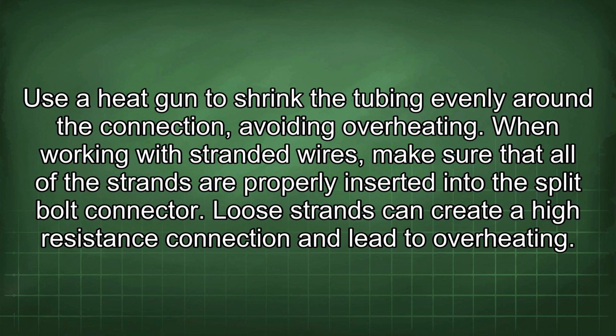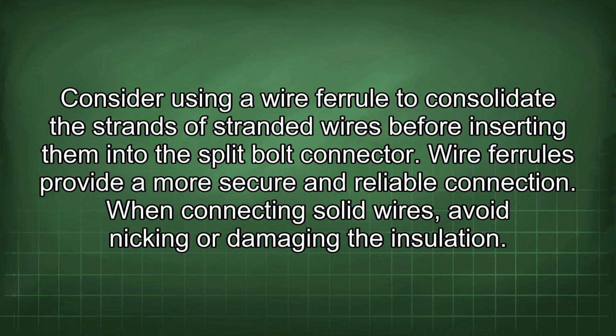When working with stranded wires, make sure that all of the strands are properly inserted into the split bolt connector. Loose strands can create a high resistance connection and lead to overheating. Consider using a wire ferrule to consolidate the strands of stranded wires before inserting them into the split bolt connector. Wire ferrules provide a more secure and reliable connection.